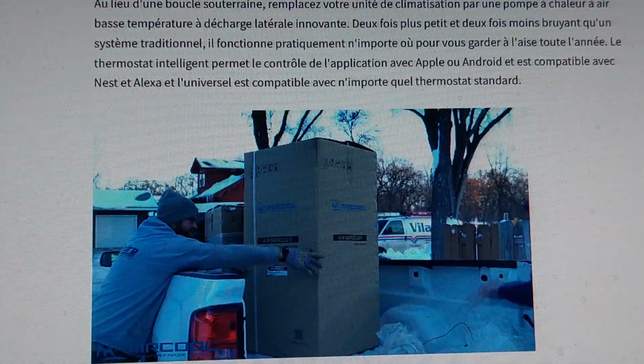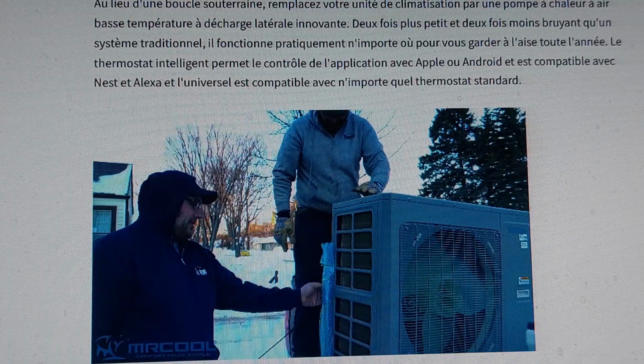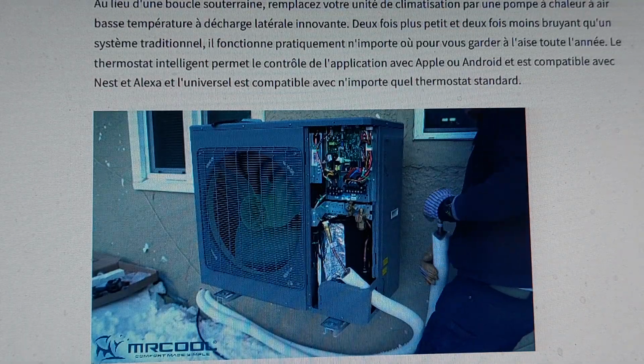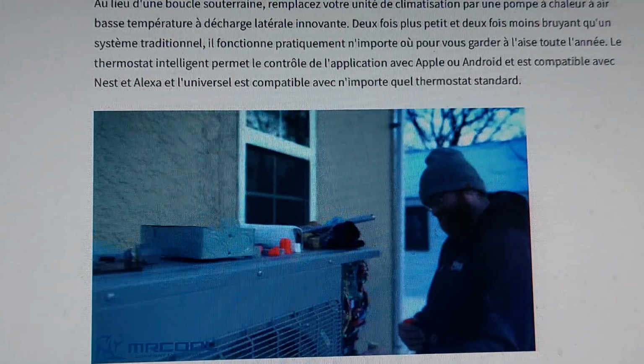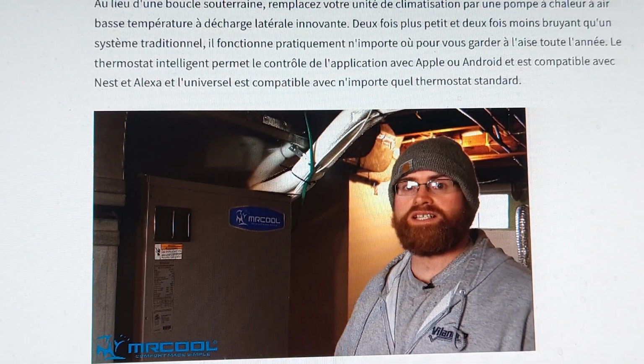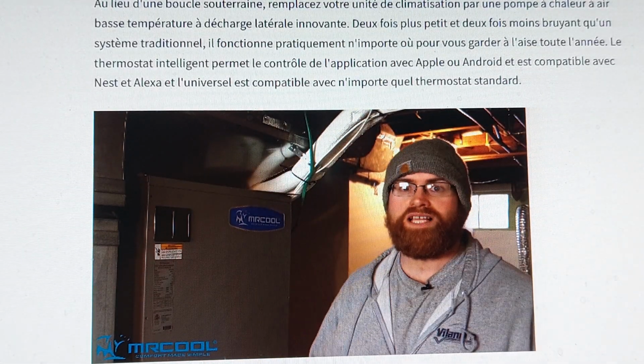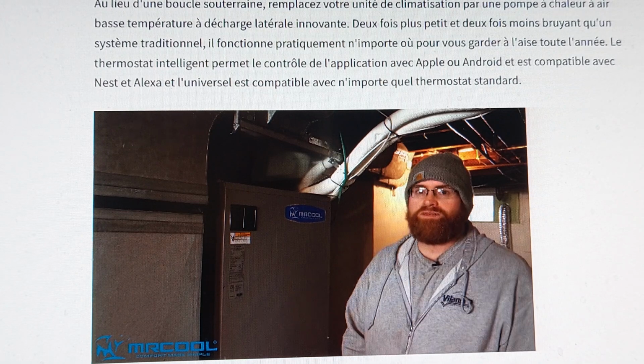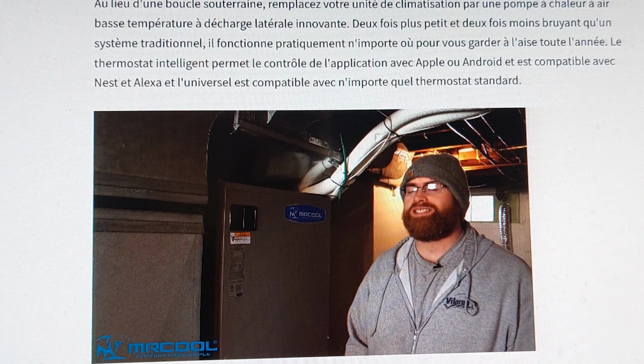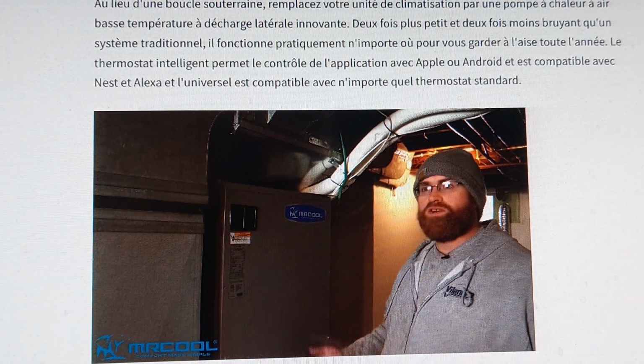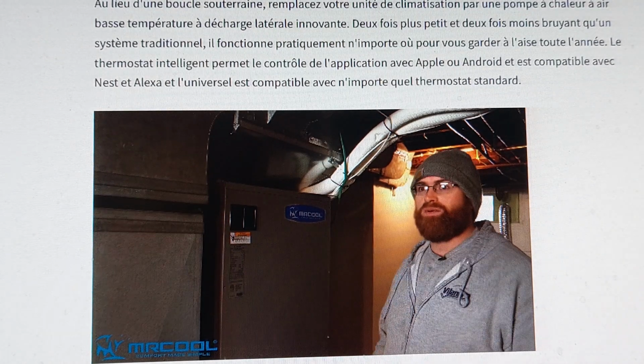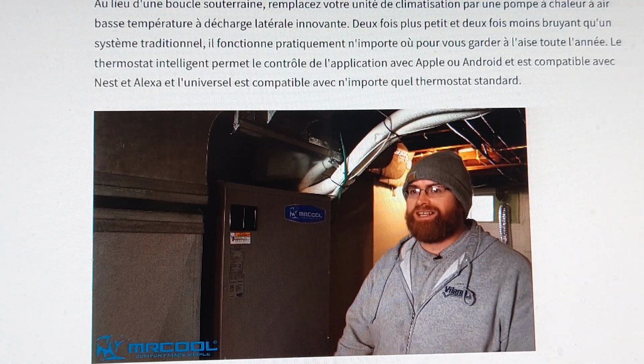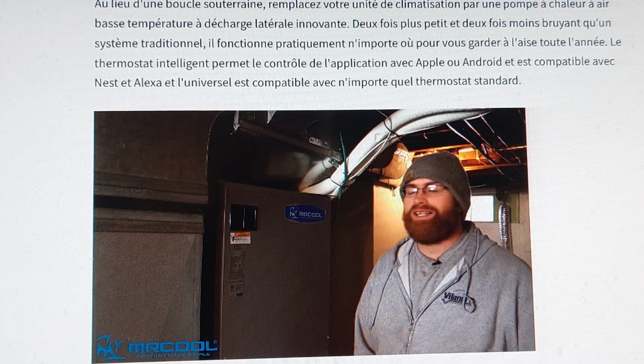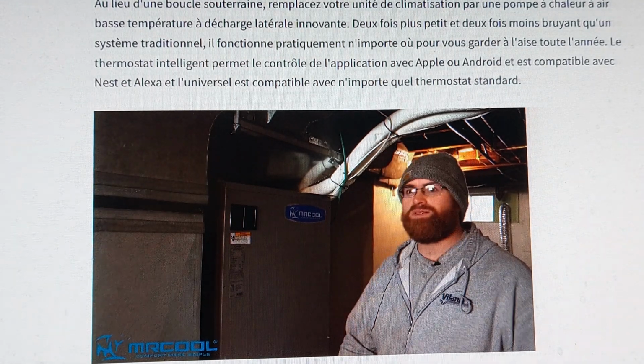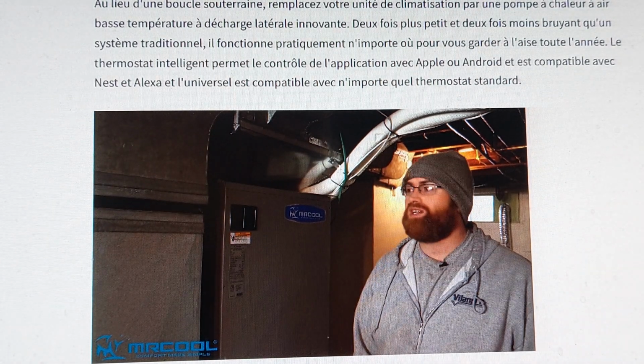I was 100% skeptical on what the unit would actually be able to do. With the cold that we get here, I've never seen a heat pump put up this kind of heat at those temperatures. Considering we just had a 32-degree split across the unit with 6 below outside, I'm impressed that it would even maintain temperature in an old house like this, considering it's a real world application. Because it's not a well-insulated house, it's old. There's no other way to put it. It's not nice, clean ductwork, it's an old system, so I'm impressed with what it will do.